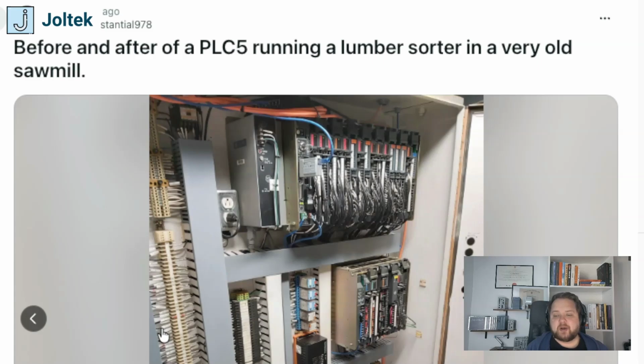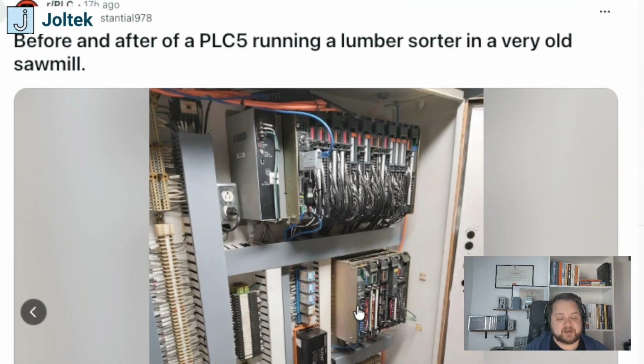So my general comment is that this is something I would expect to be migrated to a newer either CompactLogix or ControlLogix platform instead of being left on PLC 5.